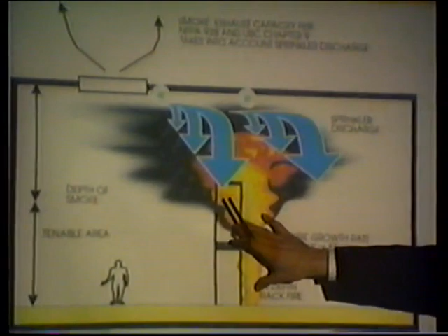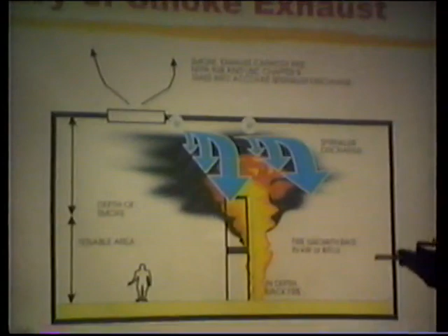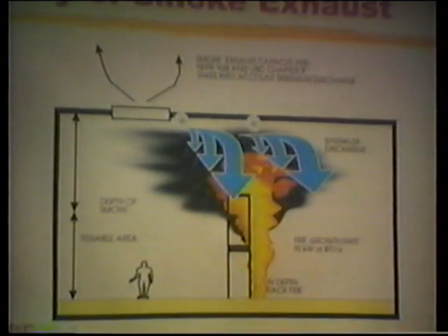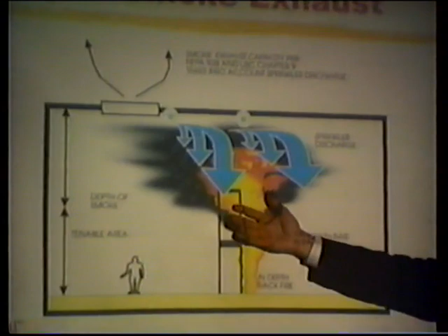One of the things we know is that as we calculate the fire growth rate, we can calculate the amount of entrained air and the subsequent smoke output of a fire at a given size. So if we hit a fire, all other things being equal, the size and space being equal, at a much smaller size, you're going to put out less smoke. Subsequently, you might be able to reduce your exhaust capacities. Okay? And that comes into a lot of play. If you've looked at the Uniform Fire Code, for example, and you followed their formula, you'd have an awful lot of holes in the roof.